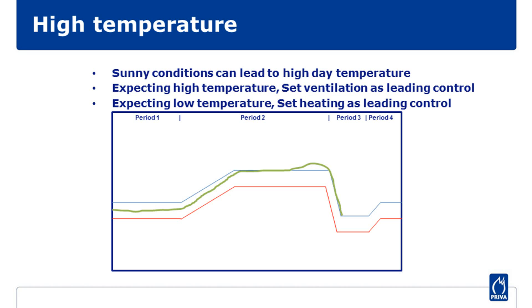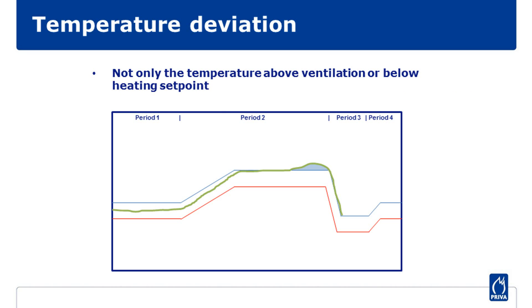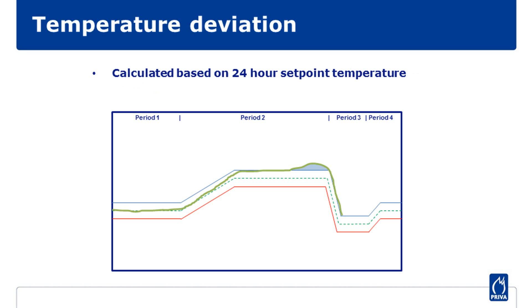Depending on what you expect, you can select the ventilation or heating strategy as the lead for the realisation of temperature. If you expect high temperatures, set the ventilation as leading. If you expect low temperatures, set the heating as leading. In the graph, the measured glasshouse temperature is now displayed until the end of the second period. You will also see that the sunny conditions create a temperature deviation at the end of the second period. However, deviation is not only the area above the ventilation setpoint — the temperature deviation is the area above the expected temperature.